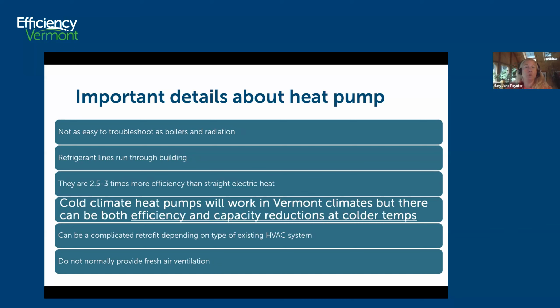Cold climate heat pumps will work in Vermont, but some models will have both efficiency and capacity reductions at colder temps. There are kind of like grades of cold climate heat pumps. You can pay a premium to get units that when it gets really cold out, they don't lose capacity and they maintain a pretty good COP. But you're looking at maybe a $2,000 to $3,000 premium on that.